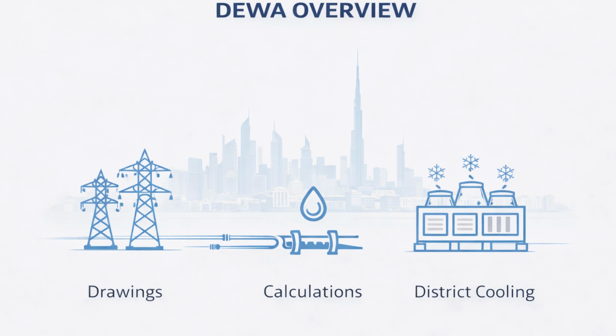DEWA looks for one thing first: numbers. They care about electrical load calculations, they care about connected load and demand load, they care about diversity and demand factors, they care about transformer and feeder capacities, they care about water demand and peak consumption, they care about network availability and spare capacities. Their main question is very simple: can the network support this building? If the answer is no, the submission stops there.